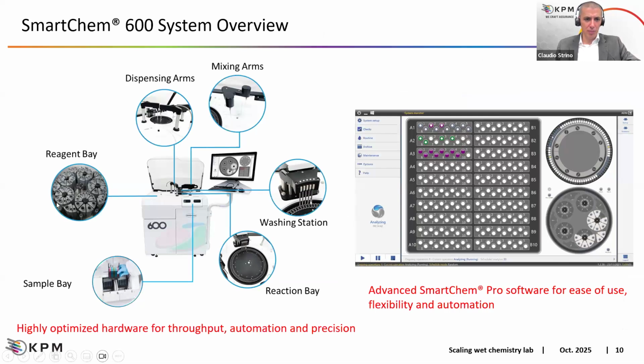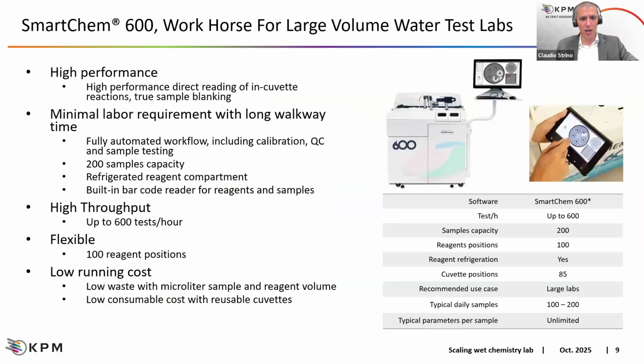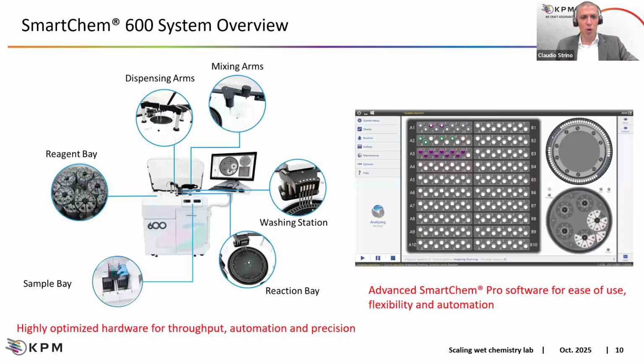The reagent bay, this is the reagent compartment, and the sample bay. As we can see, the sample compartment has been divided into 2 different compartments. Why? To really guarantee true sample addition to the ongoing routine, because while the instrument is working on the first carousel, we can load the first set of 100 samples.